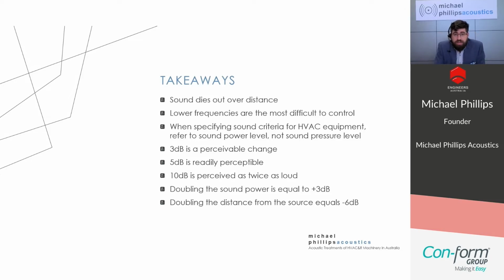So the takeaways that we have here: sound dies out over distance. Lower frequencies are more difficult to control. When specifying sound criteria for HVAC equipment, refer to sound power level, not sound pressure level. 3 dB is a perceivable change. 5 dB is readily perceivable. 10 dB is perceived as twice as loud. Doubling the sound power is equal to +3 dB, and doubling the distance from a source equals -6 decibels.